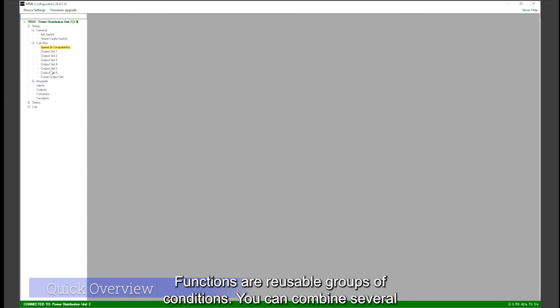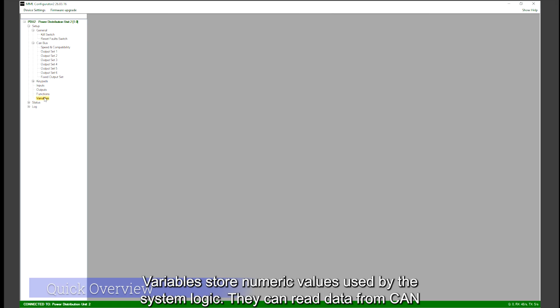This is where you configure CAN bus speed and other parameters, which we'll discuss later in this video. PDU units have 2 different CAN buses that can operate at different speeds. Functions are reusable groups of conditions. You can combine several conditions into a function once and then use that function anywhere instead of repeating the same conditions multiple times. Variables store numeric values used by the system logic. They can read data from CAN, analog inputs, or other variables and convert it into values that can be used in conditions or output control. We will talk about these later on in the video, where we focus more on the advanced features.